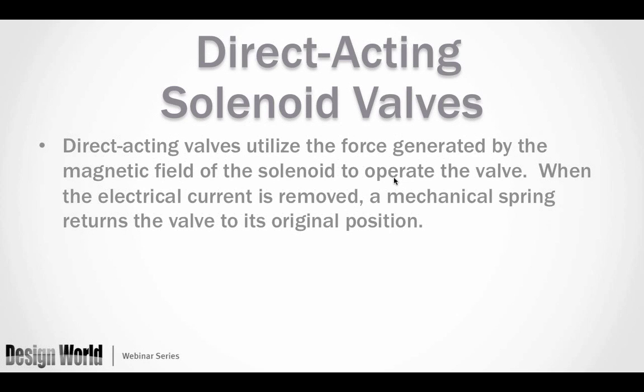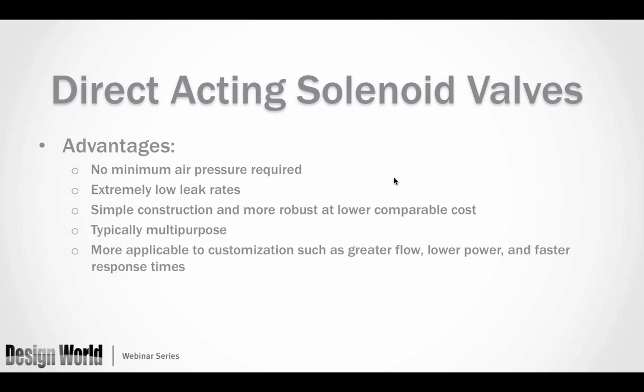Indirect acting valves offer higher flow, low power consumption, greater shift forces, and a lot of variety — they are very popular today. A direct acting valve uses the force of the magnetic field in the solenoid to move the spool, poppet, or other internal element directly. You'll have either a double solenoid pushing from both sides, or a single solenoid with a mechanical spring to return the valve. Direct acting valves have no minimum pressure requirement, and can often run from full vacuum up to rated pressure, including low pressures of 5 or 10 psi.